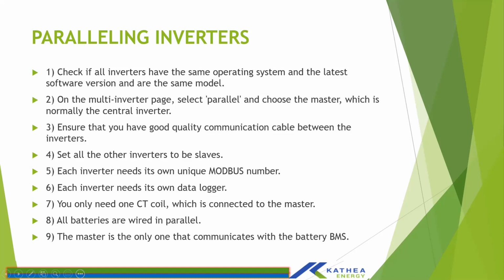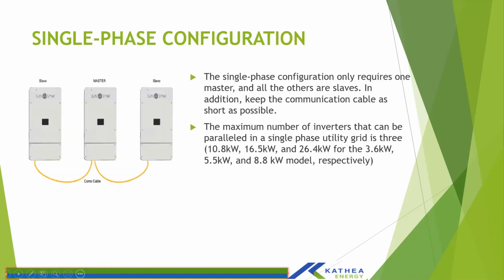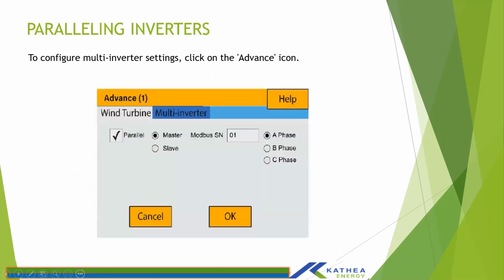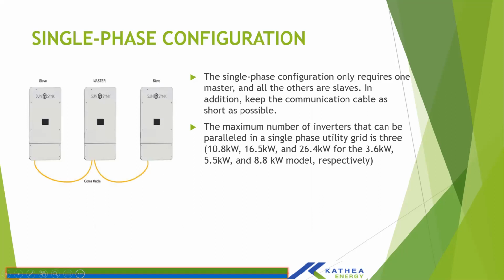So in a single phase scenario, the master is the only inverter that communicates to the battery BMS. It means your CAN bus cable, you would hook it to your master inverter. So in a single phase scenario, you would select parallel. For the master inverter, select master, set the ID, and then the phase will be phase A, for instance. Your other inverters will be slaves. You select slave, select a different Modbus ID, but on phase you tick the same phase, because they are simply producing as a single phase, on a single phase line. So basically this is the single phase configuration.